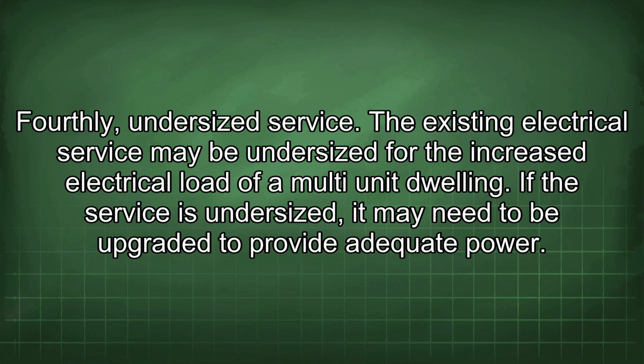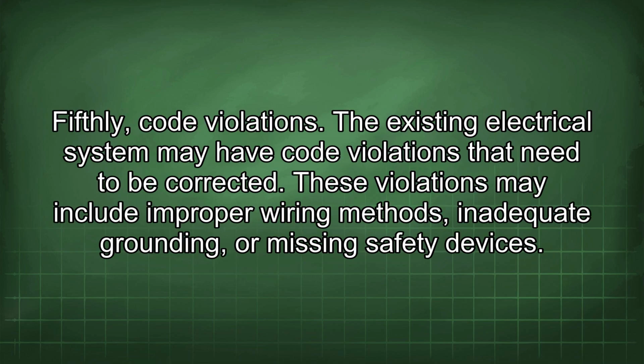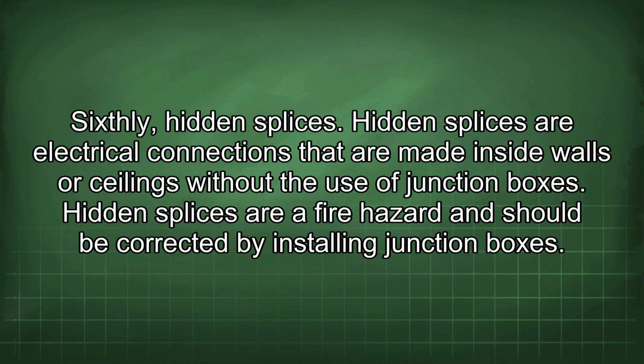Fourthly, undersized service. The existing electrical service may be undersized for the increased electrical load of a multi-unit dwelling. If the service is undersized, it may need to be upgraded to provide adequate power. Fifthly, code violations. The existing electrical system may have code violations that need to be corrected. These violations may include improper wiring methods, inadequate grounding, or missing safety devices. Sixthly, hidden splices. Hidden splices are electrical connections that are made inside walls or ceilings without the use of junction boxes. Hidden splices are a fire hazard and should be corrected by installing junction boxes.